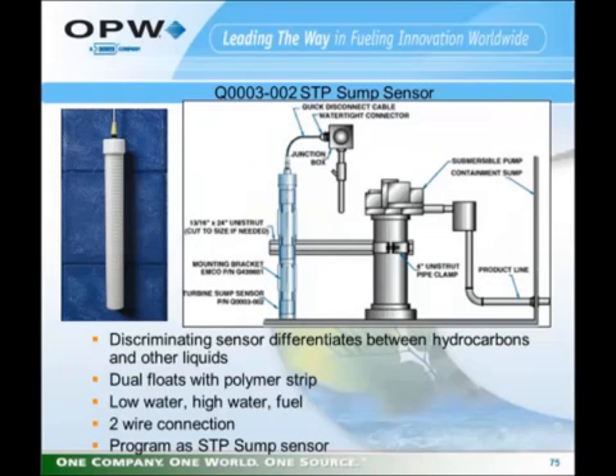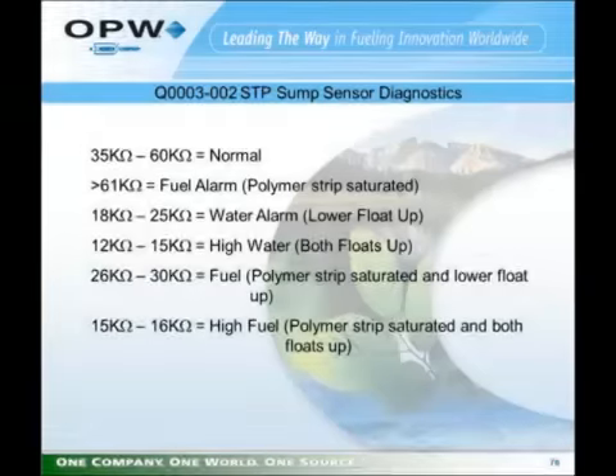The Q0003-002 is a STP sump sensor, or submerged turbine pump sensor. Essentially the same as the Q0003-001 dispenser pan sensor, except it is longer. Still has two floats, has a polymer strip. It's a discriminating sensor, detects water or hydrocarbons, and issues appropriate alarms for those. In the unit, it's programmed as an STP sump sensor. We give you resistance readings for this sensor also. If you'll notice, these are the same resistance readings that the dispenser pan sensor has. Again, these would be used for troubleshooting different states of the sensor itself.